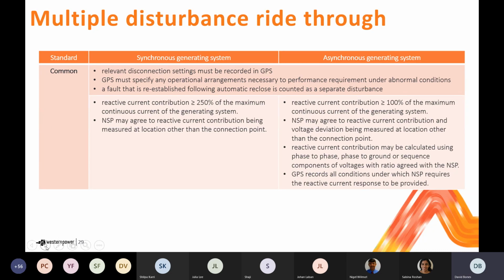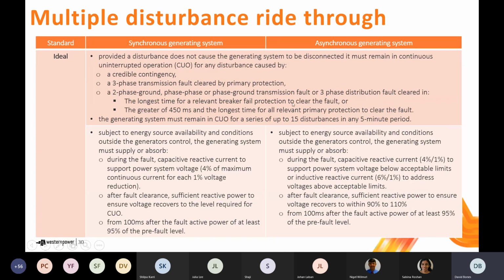We'll now move on and just have a look at the minimum. So what we were looking at there were the common provisions that apply in all cases. You'll see that for both the ideal and minimum standards, there's a requirement at the top which talks about the types of faults and the number of those faults in a period of time that need to be ridden through, or in the terminology adopted in the technical rules, for the generating system to remain in continuous uninterrupted operation. And then in the bottom half of the table, again separated by technologies, is a discussion around the level of reactive current injection that needs to be provided both during the fault and after the fault is cleared to support the control and recovery of power system voltage.